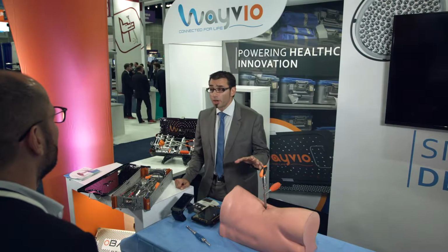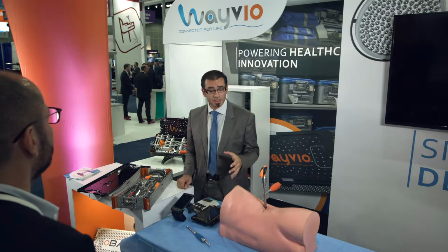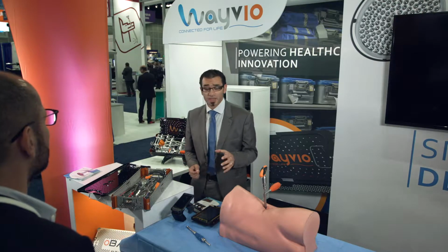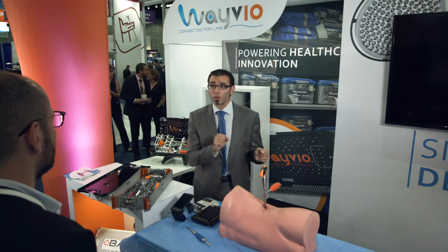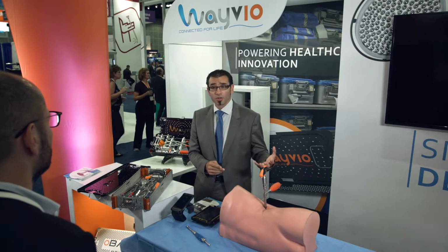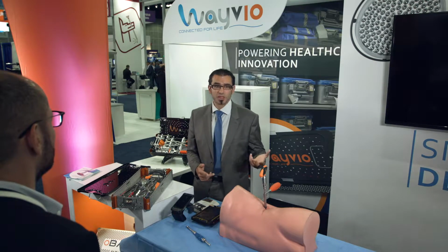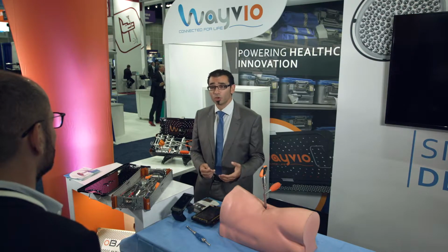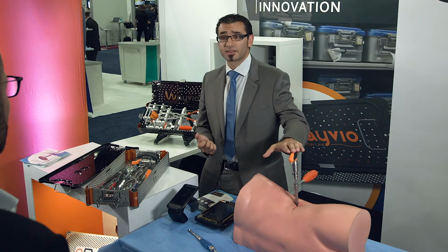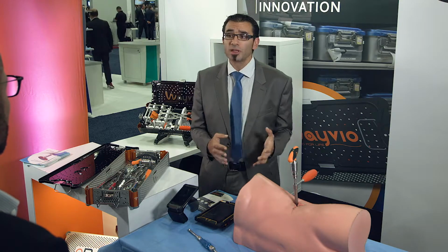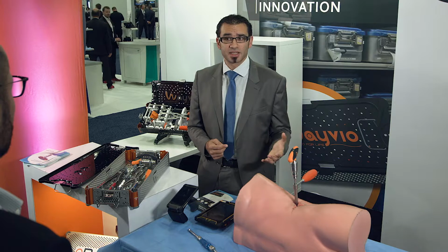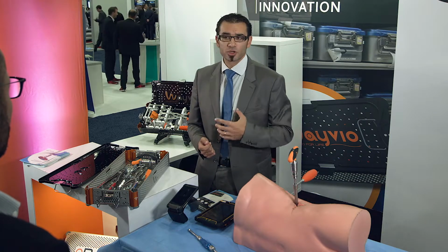From an OEM point of view, the torque limiter today is really a struggle for them, because as they don't really know how many times the instrument is used, they base their recalibration policy only on time. Every 6 months, for example, they will remove all those torque limiters from the field and replace them with other instruments. It takes time, it takes money, and in fact, maybe half of those instruments just stayed on the shelf. So you take those instruments and pay money to recalibrate them, and maybe they've never been used. With that technology, you will recalibrate those instruments only when they are really, effectively used. So let's say instead of having a 6 months policy for recalibration, you will have a 1,000 releases policy. So for sure they will save money.